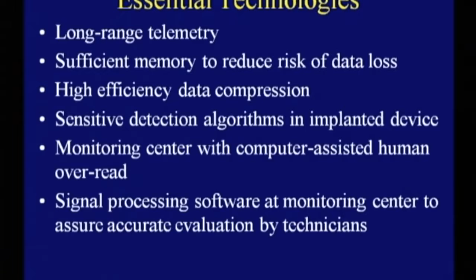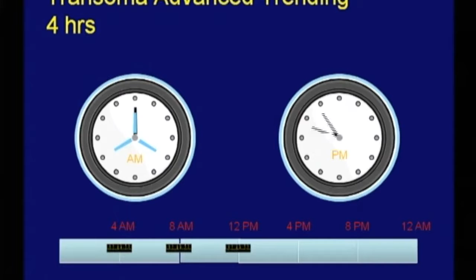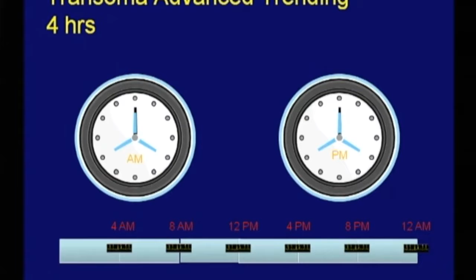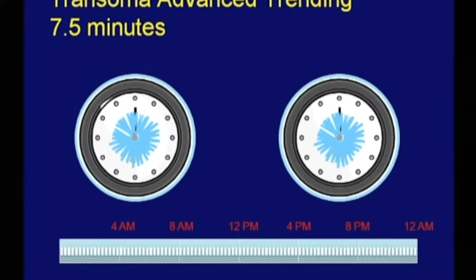One of the features of this device is that it captures rhythm strips on a regular basis. This is an example of one programmable mode where this is capturing rhythm strips at 4-hour intervals. These rhythm strips are then transferred from the implant to the handheld device and then forwarded on to the service center. They can be captured at intervals as frequently as 7.5 minutes.